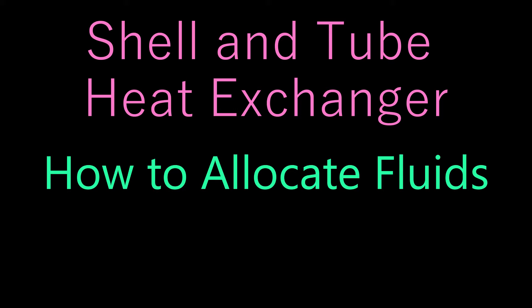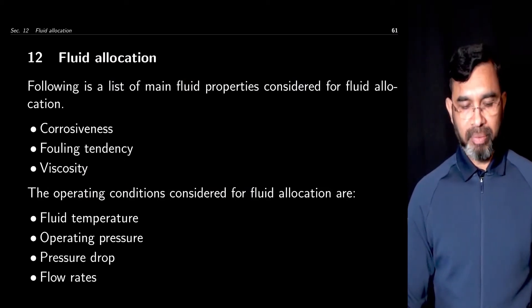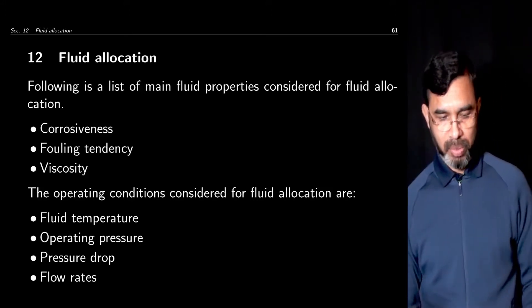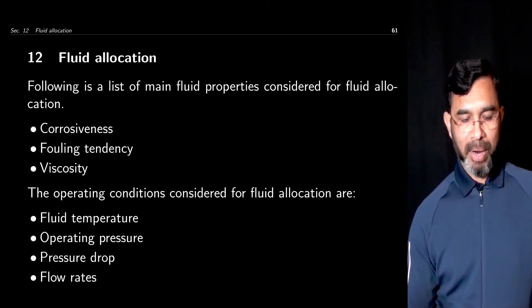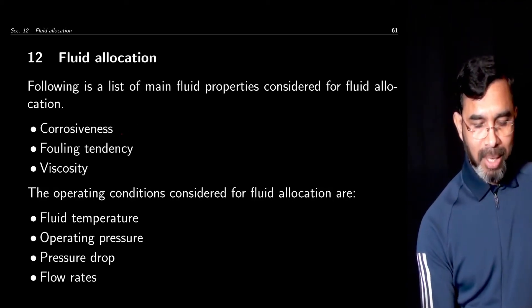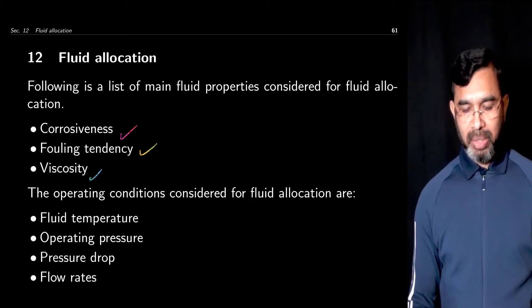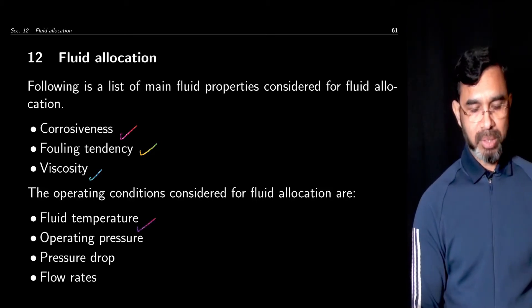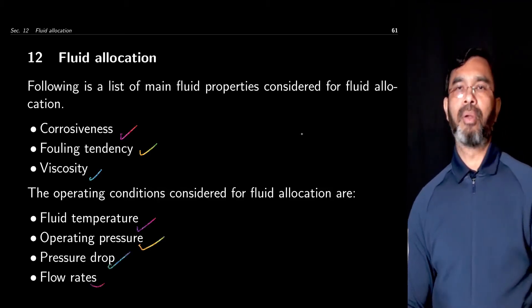In this session we talk about how to allocate fluids on the shell side and on the tube side. For doing that we consider different fluid properties and also different operating conditions. Among the fluid properties the three mainly considered are corrosiveness, fouling tendency, and viscosity. The main operating conditions considered are the temperatures of the two streams, the operating pressure, the pressure drop, and the flow rates.